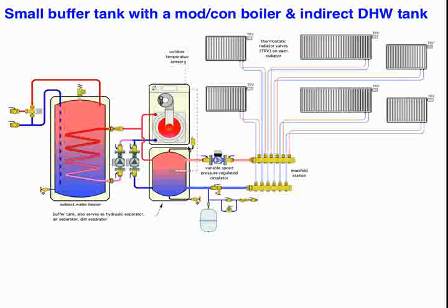We have a dedicated indirect water heater here. We also have a thermal mass, a small buffer tank that is perhaps a 25-gallon buffer tank matching up with our previous example. And over here on the right, we've got a variable speed circulator. We're going off to a manifold distribution system serving panel rads with thermostatic radiator valves.